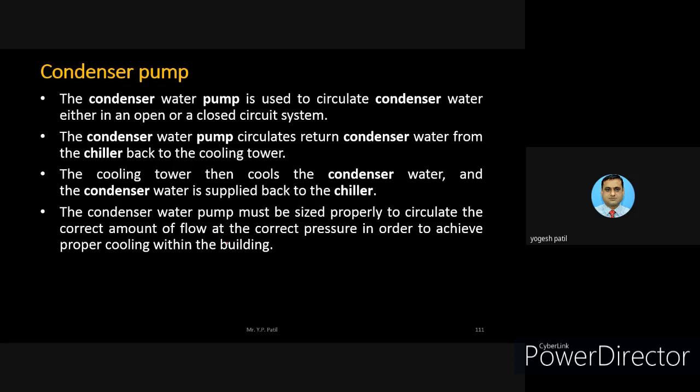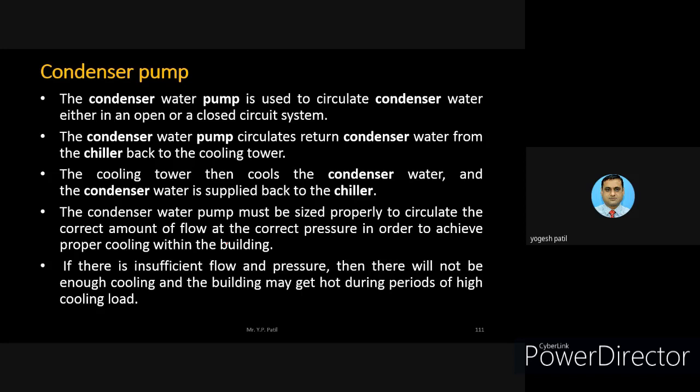Why are the pumps and the control of the pumps important? To maintain the proper flow rate as well as the proper pressure. To maintain these two things, the condenser pumps must be properly sized. If there is insufficient flow and pressure, then there will not be enough cooling and the building may get hot during periods of high cooling load. When the cooling demand is high and this condenser pump is not properly sized, there will be insufficient flow and pressure, and because of that cooling will not be proper. So this is why the condenser pump is important.